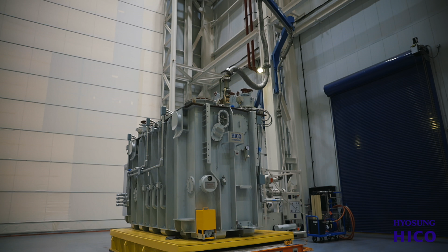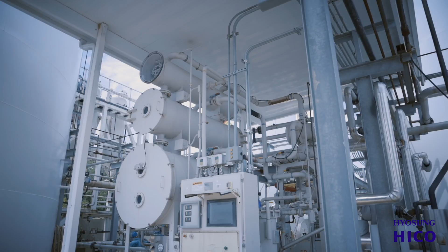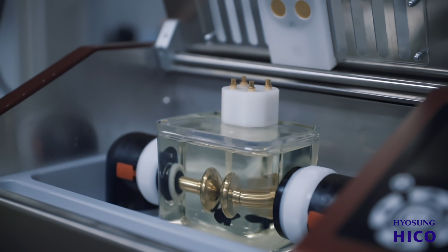My name is Kamisha Terrell, and I'm a quality inspector at Hyosung HICO. So DGAs are dissolved gas analysis samples. Oil samples are typically taken from the tank farm or the transformer. 15 milliliters of oil are placed in vials that are purged with argon. At that point, those vials are placed into a headspace which agitates those samples. The analytes are picked up by the detectors on the GC machine. Results are displayed on a chromatogram.